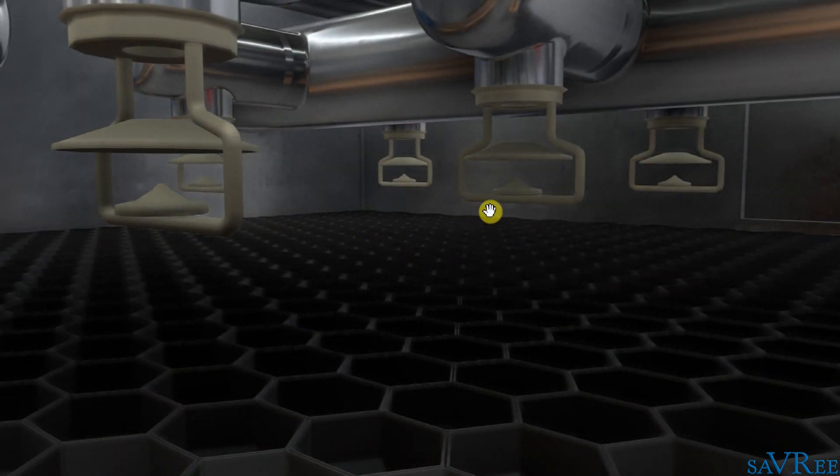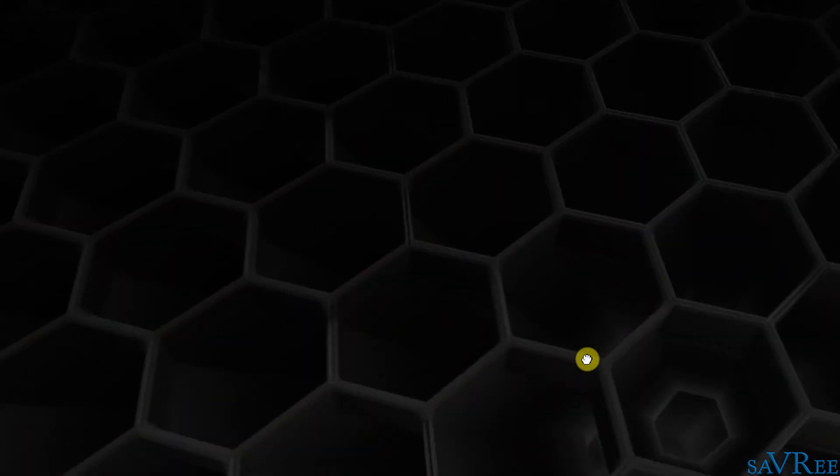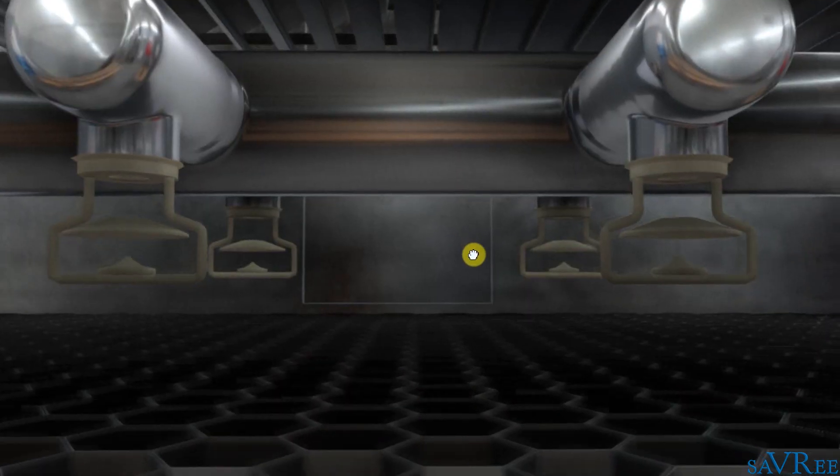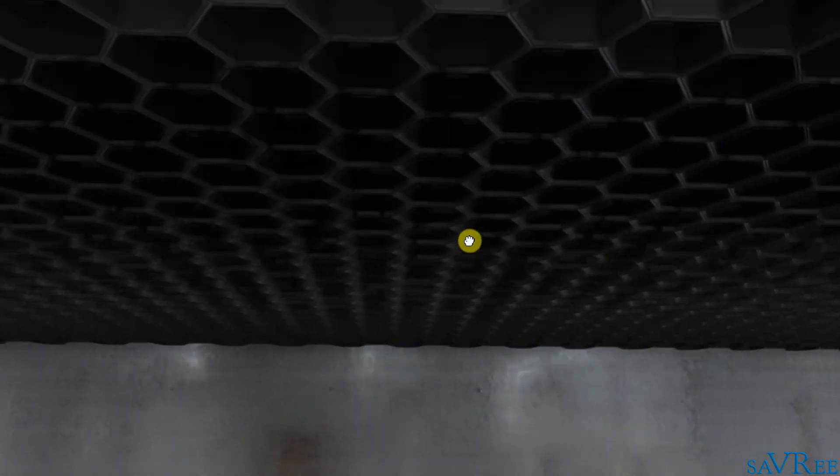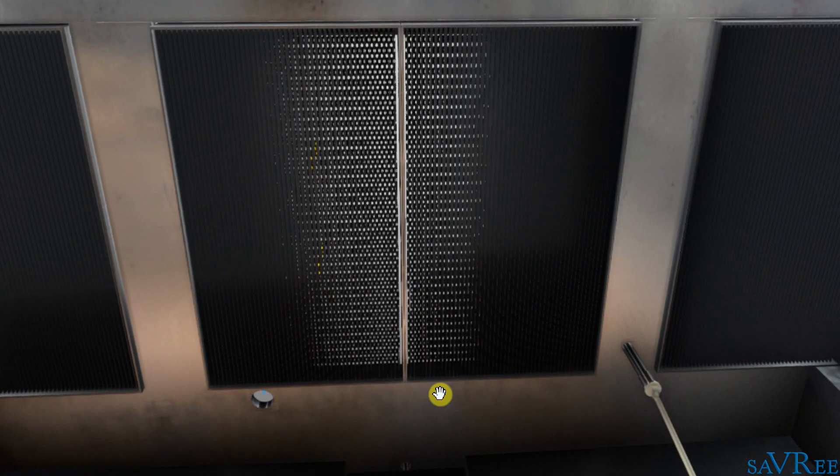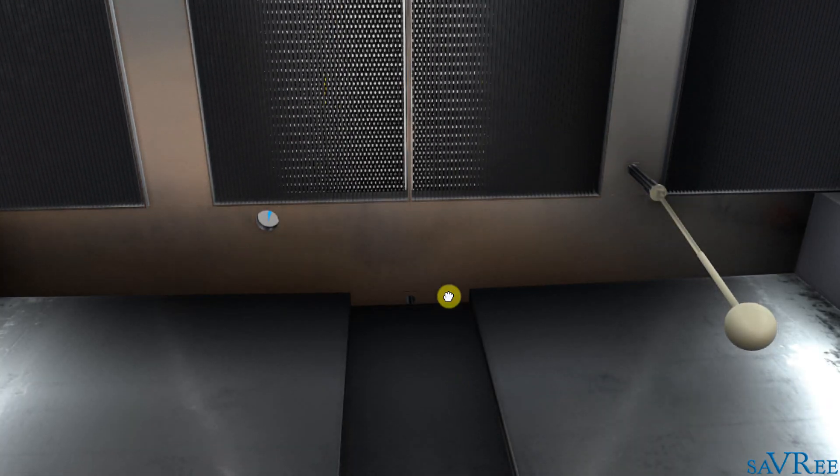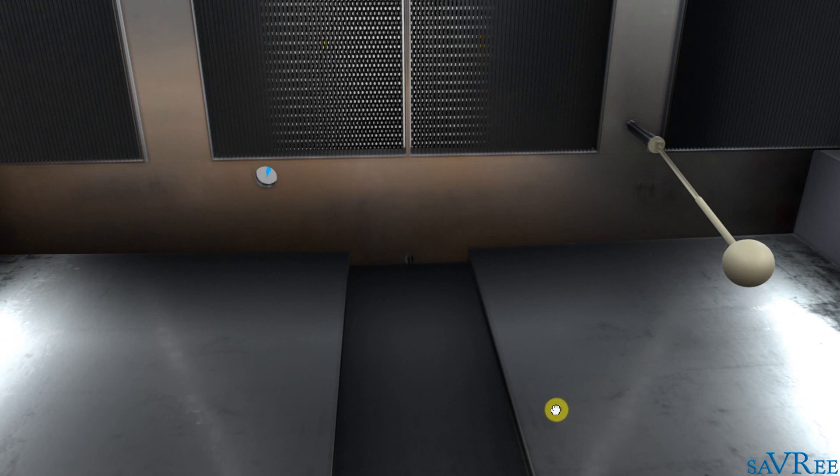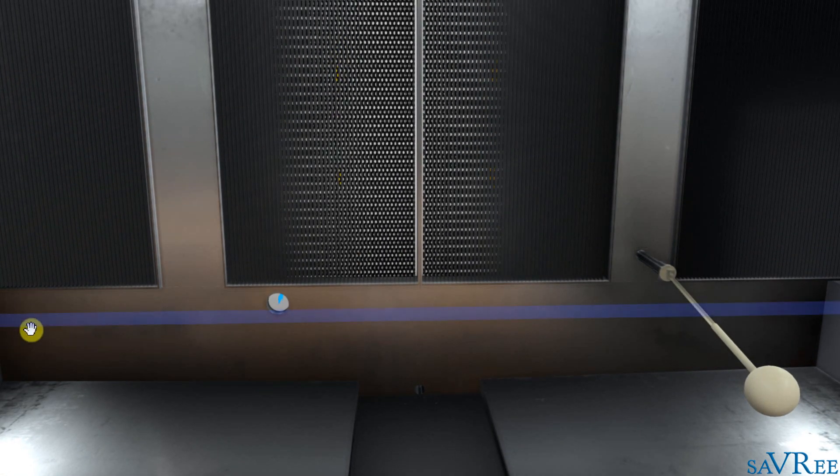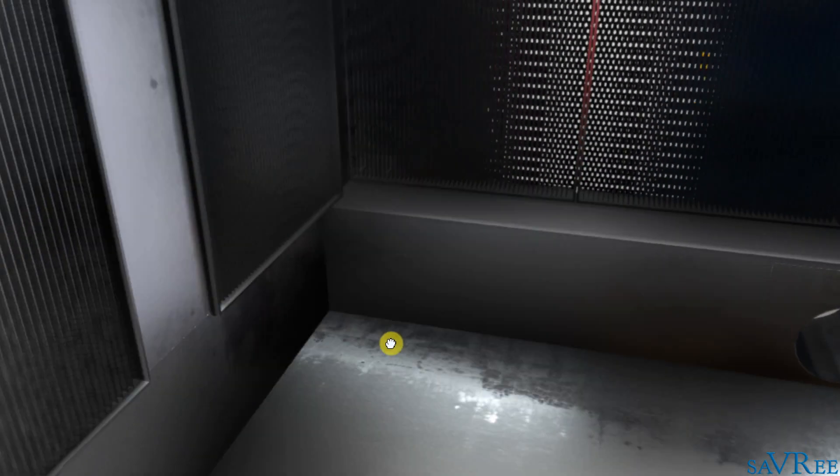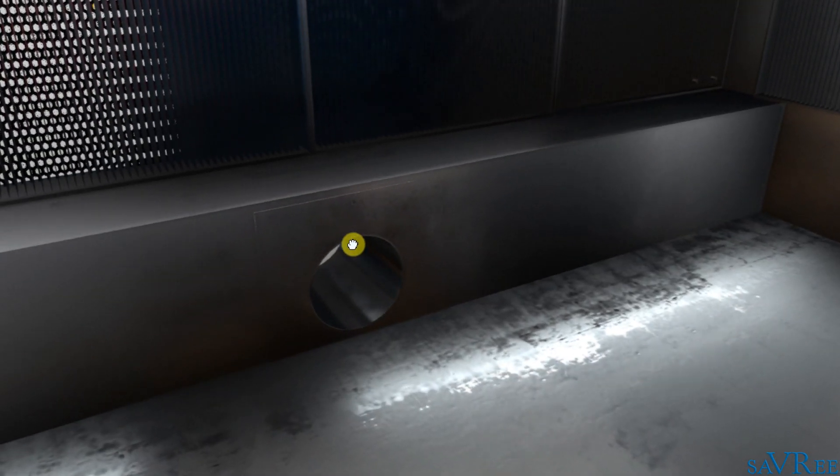So the water has been sprayed out of these nozzles, spread across a large cross sectional area. It's now going to drip into the fill and pass through the fill and drop out the base of the fill. It's only flowing due to gravity as it passes through the fill. So let's go down through the fill, this honeycomb type structure. And as we go down, you can see we've now come out the other side. The honeycomb type shape is much the same. And the water is going to drip down and fall into our cooling tower basin. It's going to fall into the area around here, and we might have a water level that is approximately at this level here.